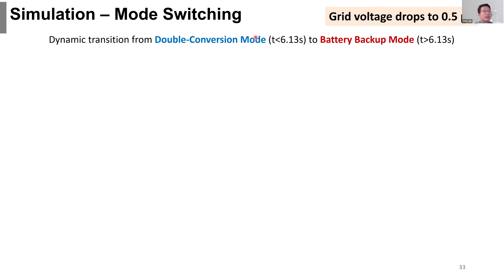The second simulation result is we simulate a voltage drop to 0.5 per unit, and in this case we switch from the double conversion mode to the battery backup mode. Looking at the left figure, this red curve is the grid side voltage jumping from 0.7 to 0.5. If we do not do the mode switching, the AI computing load cannot be directly connected to the 0.7 or 0.5 per unit voltage - that would trip the AI computing load. But through the mode transition, when we switch to battery backup mode, we can still maintain the load side voltage at close to 1 per unit.